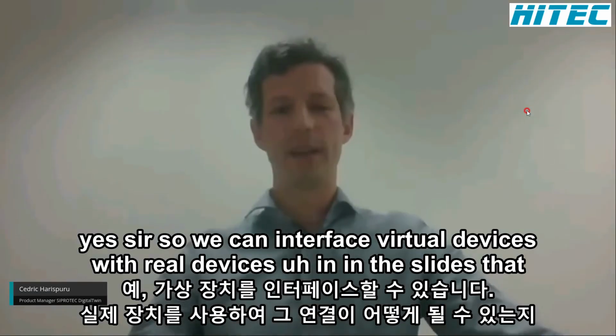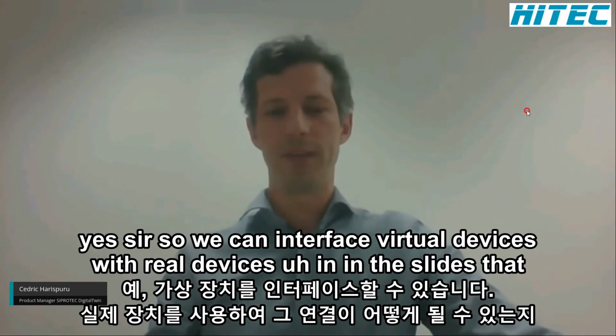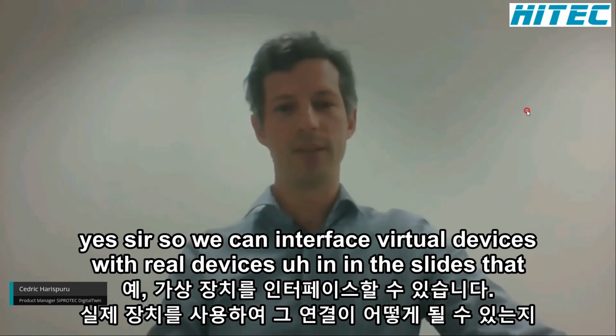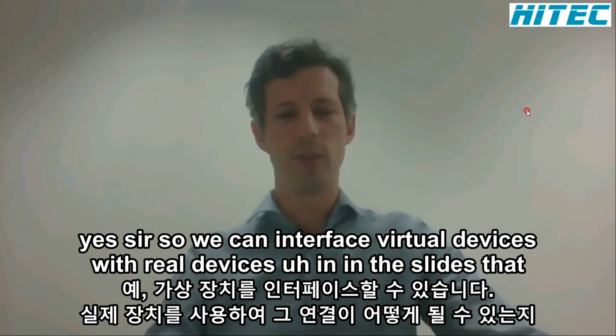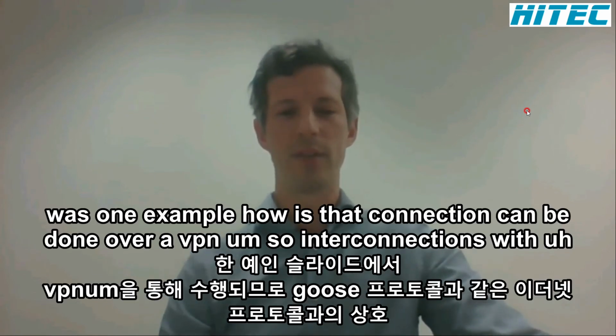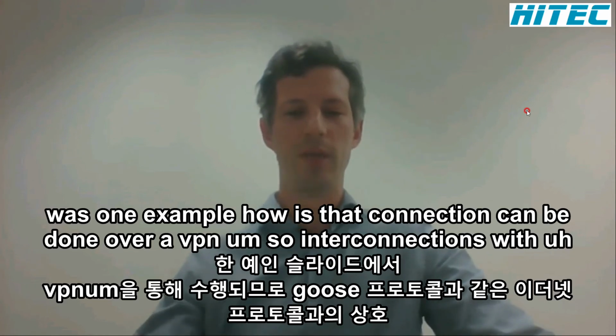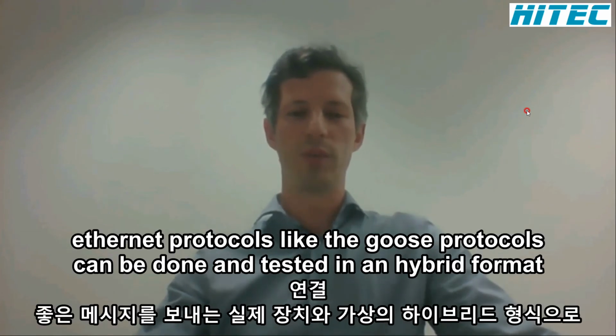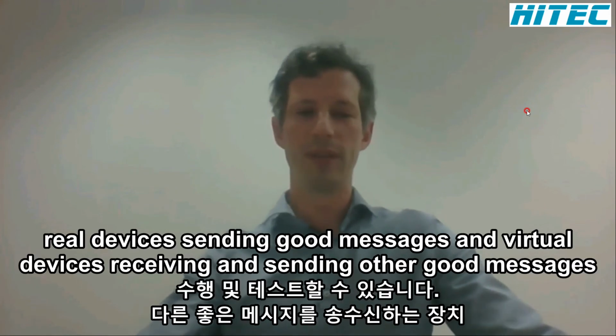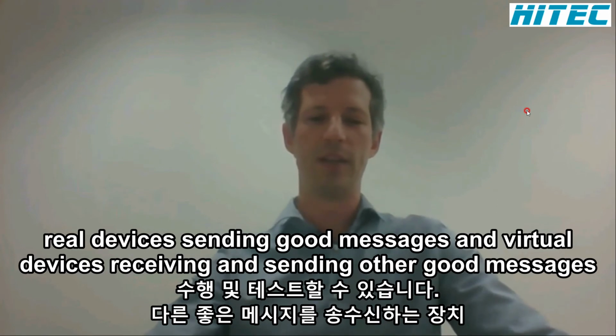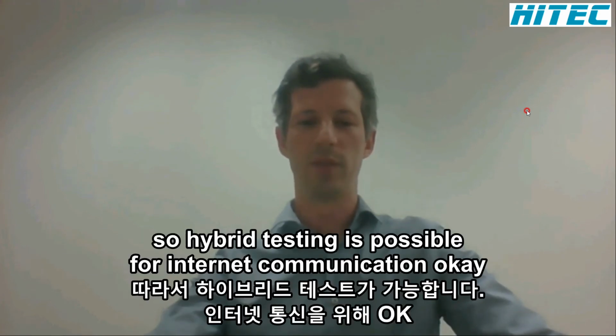Yes, we can interface virtual devices with real devices. In the slides there was one example of how that connection can be done over a VPN. Interconnections with Ethernet protocols like Goose can be done and tested in a hybrid format—real devices sending Goose messages and virtual devices receiving and sending other Goose messages. So hybrid testing is possible for Ethernet communication.